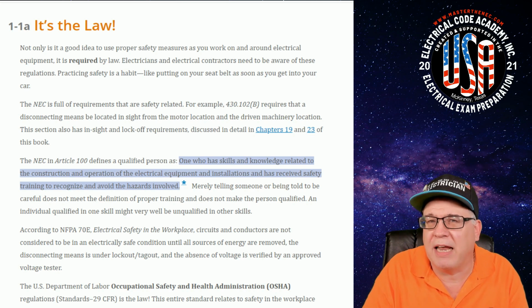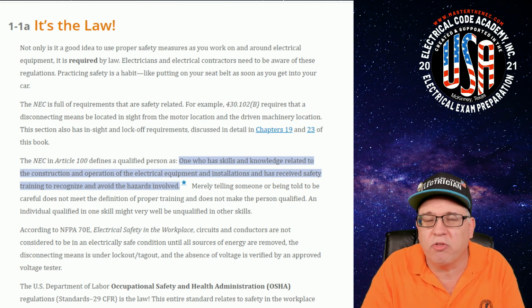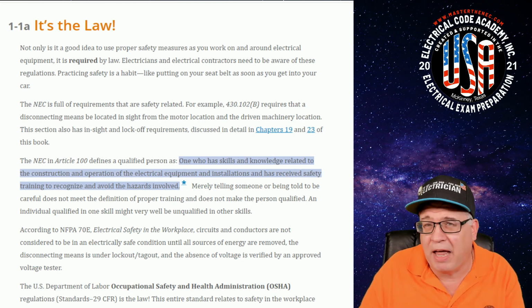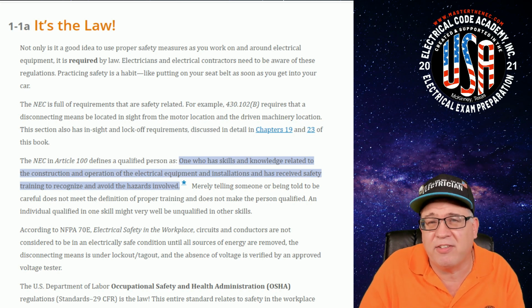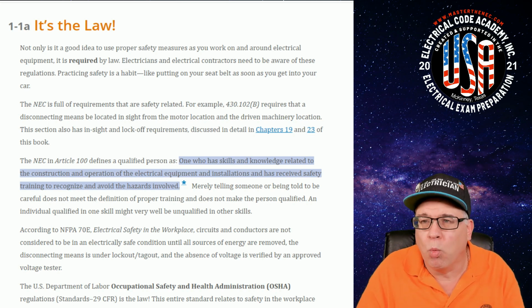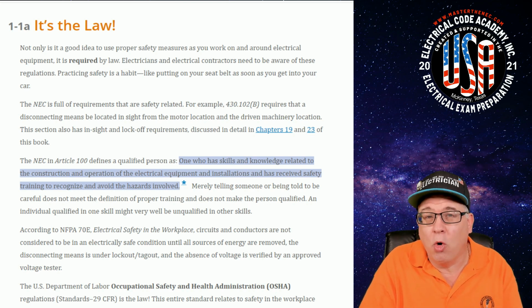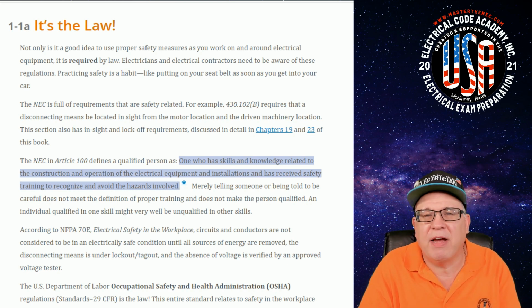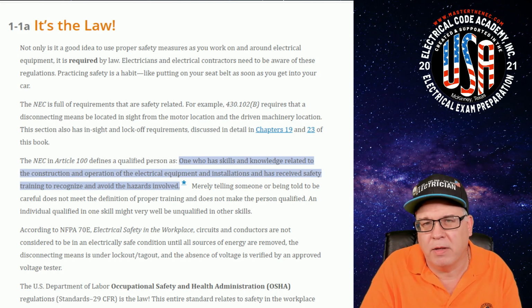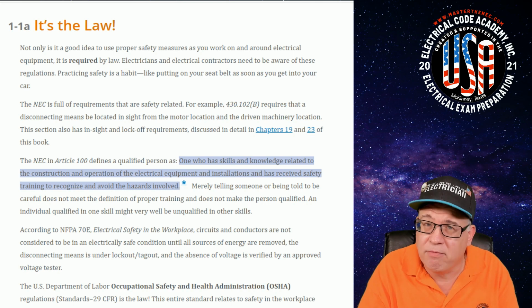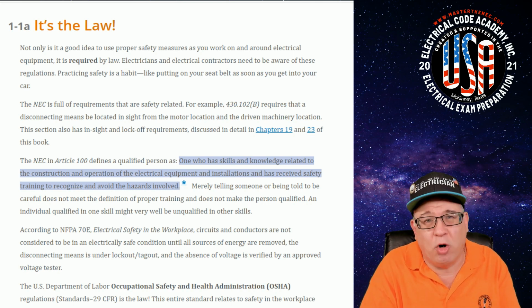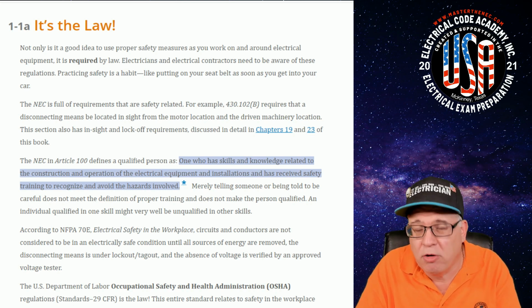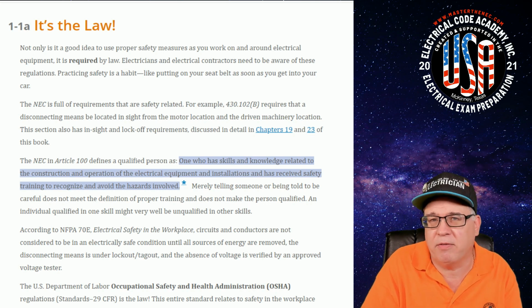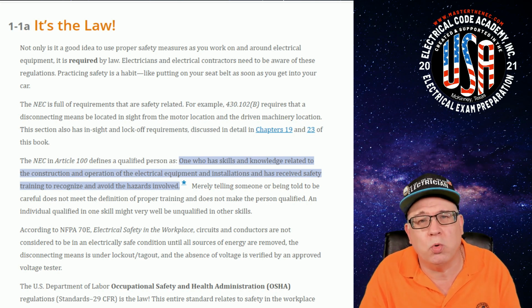There are allowances in the code where an appliance needs a disconnecting means, and we'll let you have that disconnect either within sight, or if it's not within sight, you have to have a lockout procedure following the rules in 110.25. You're going to lock the circuit in an open position, and that can be utilized to safely work on that piece of equipment. So we do have some rules to follow, and they're all very much safety driven.